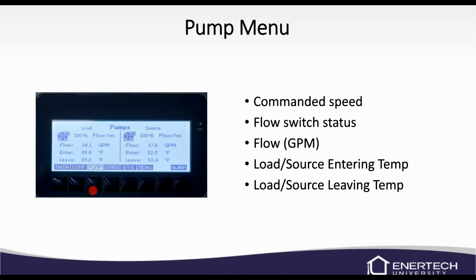The pumps menu, press the button underneath the pumps, and it'll tell you the commanded speed, whether your flow switch is open or closed. It'll say yes or no. The flow in GPM, and your entering and leaving water temperatures.